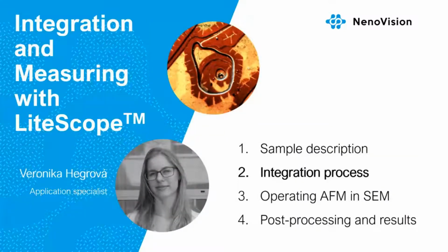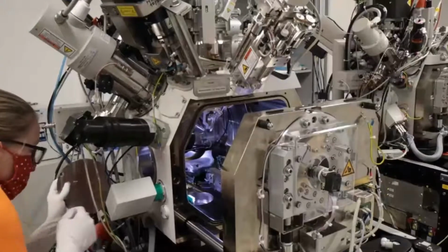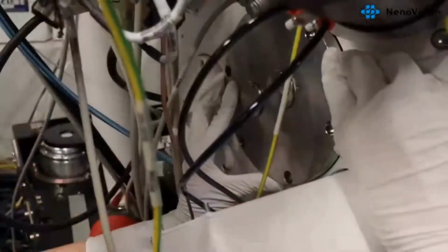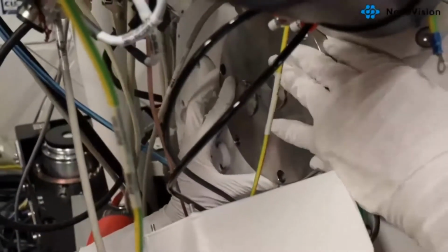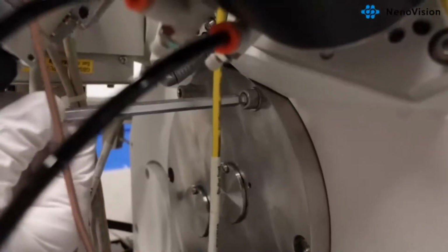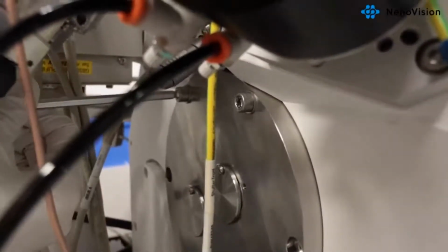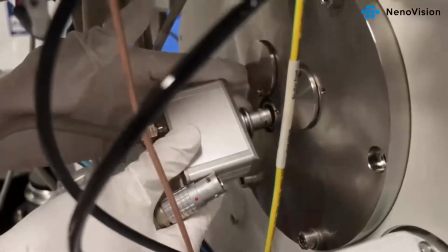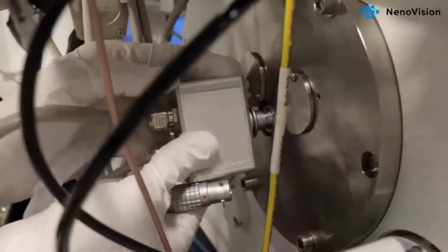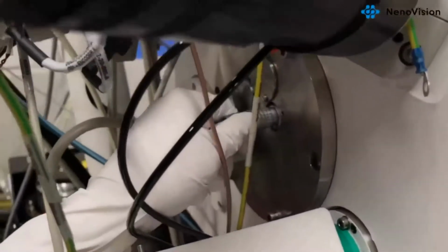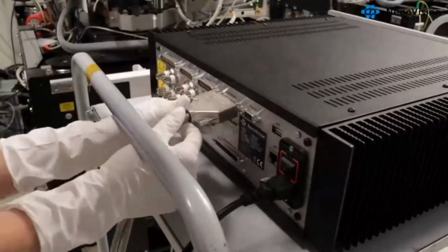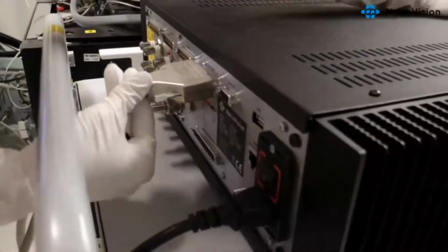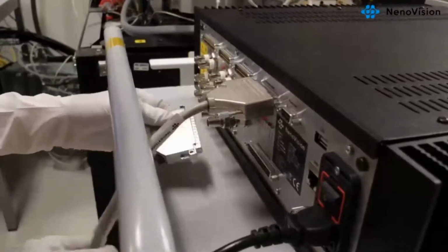Before we start measuring the samples, let's have a look at how to integrate the AFM microscope into the SEM. I am going to start with an integration into one of the Thermo Fisher scanning electron microscopes. To maintain the chronology, I start with the procedure of exchanging the flange with the feed-through and cable connection from the feed-through to the controller, Nanobox. These steps have to be done only the first time, because the outer connection does not interfere with the SEM when LiteScope is not in use, so we don't need to remove it.